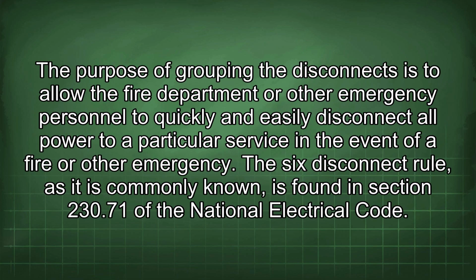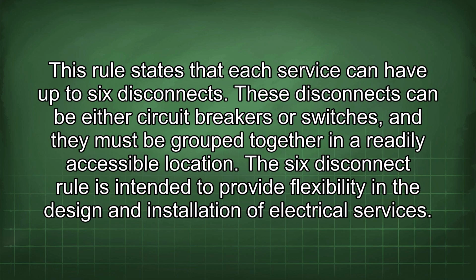The purpose of grouping the disconnects is to allow the fire department or other emergency personnel to quickly and easily disconnect all power to a particular service in the event of a fire or other emergency. The 6 disconnect rule, as it is commonly known, is found in Section 230.71 of the National Electrical Code. This rule states that each service can have up to 6 disconnects. These disconnects can be either circuit breakers or switches, and they must be grouped together in a readily accessible location.